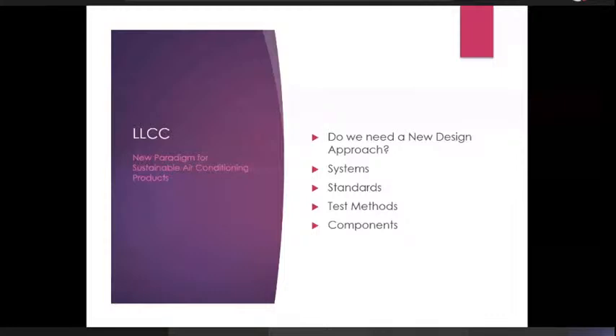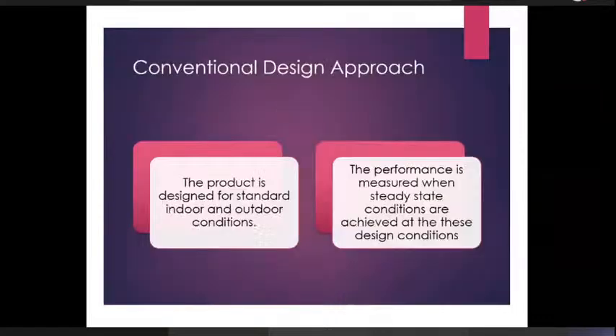The conventional design approach is what? The product is designed for standard indoor and outdoor conditions. As I said, when I'm designing in the conventional way, I have a number to hit. If I want to hit 3.3 EER at design conditions, once I've hit that number, my job is done. And the product then goes to the next phase. Release to production, then production looks at everything, and then it is going to market. And in market, it is going to be audited.